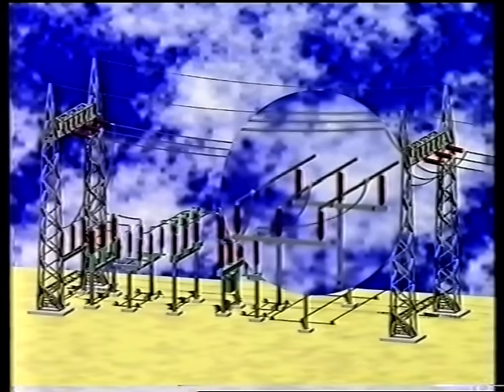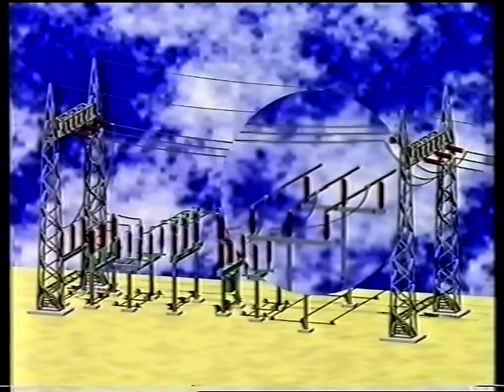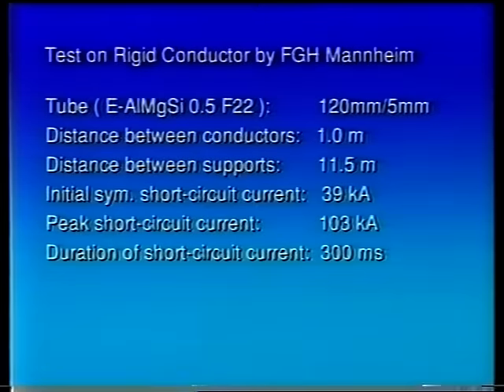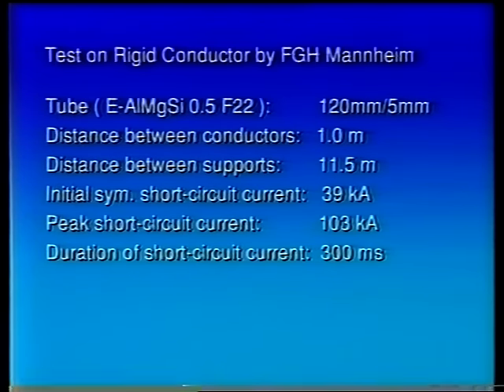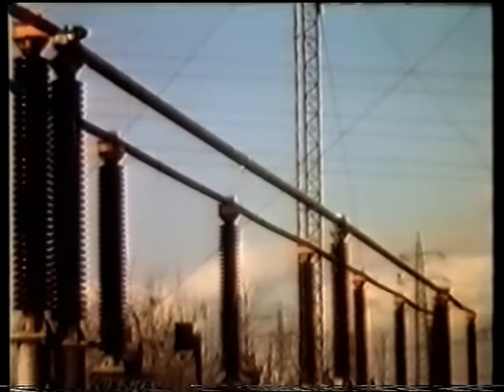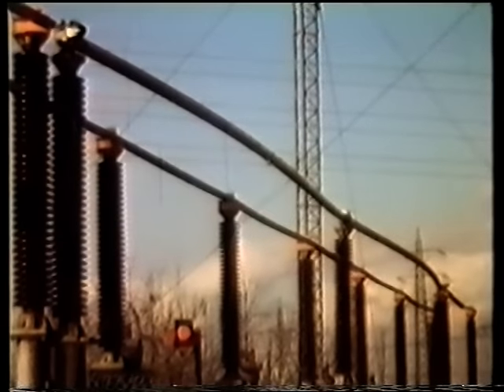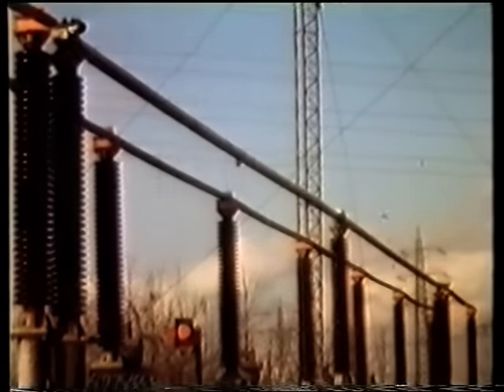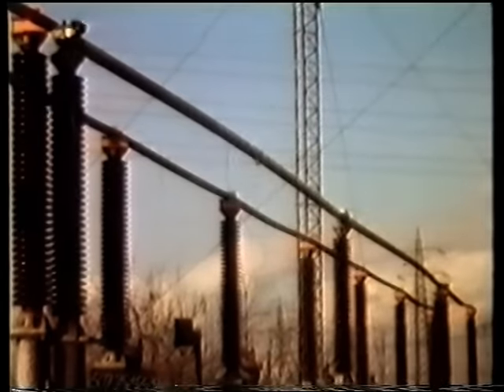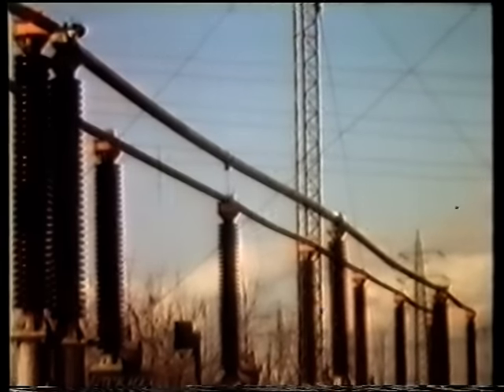This first test shows the effects on a bus bar made from tubular aluminium, with an outer diameter of 120 millimetres and a centre line distance between supports of 11.5 metres. The root mean square value of short-circuit current is 39 kiloamperes, with a duration of 300 milliseconds. This means that the peak short-circuit current of the line-to-line fault is 103 kiloamperes, which causes high stresses in conjunction with high amplitudes for the displacement of the tubes. The insulators are still strong enough to keep forces and bending moments.